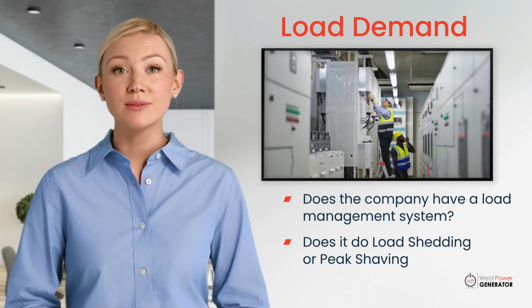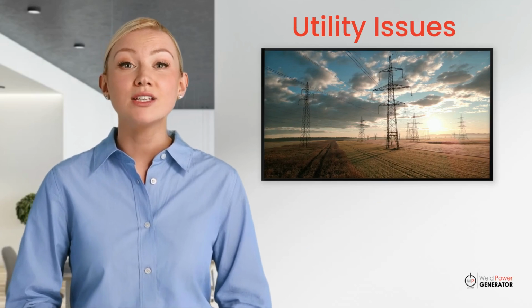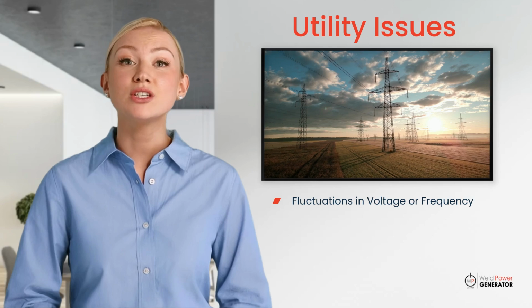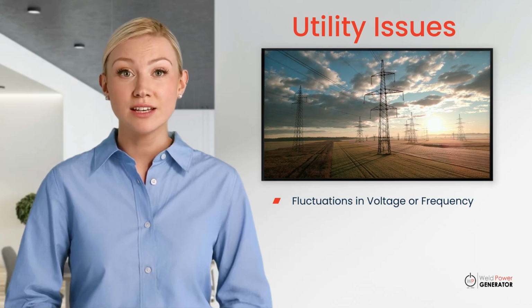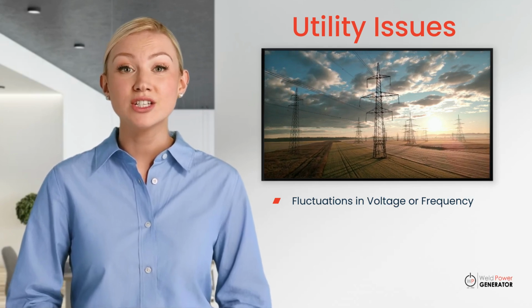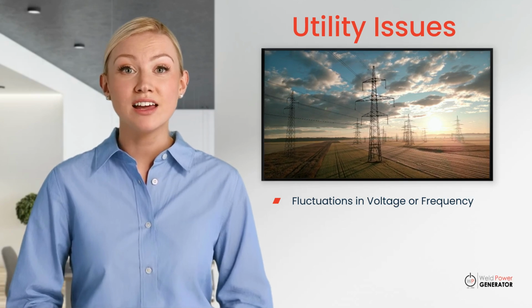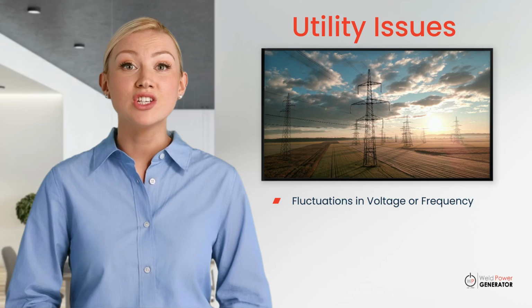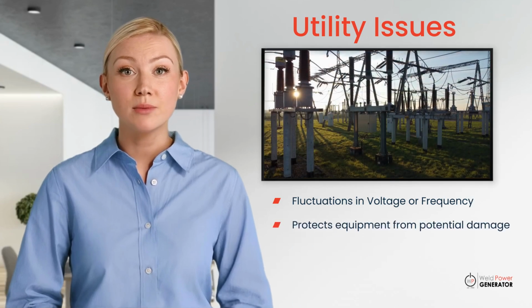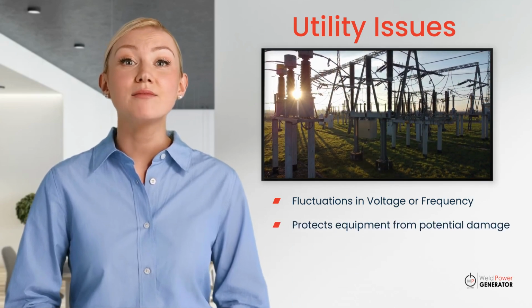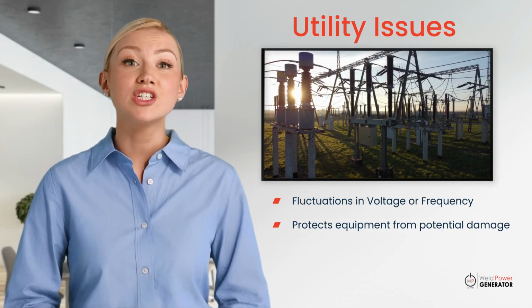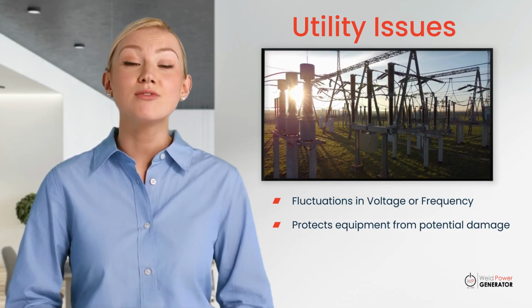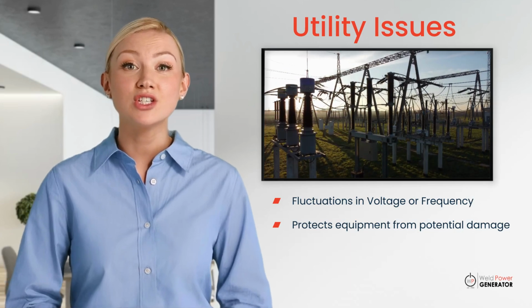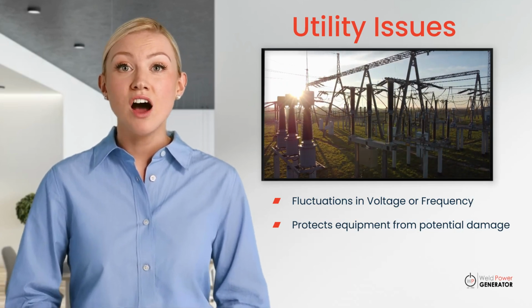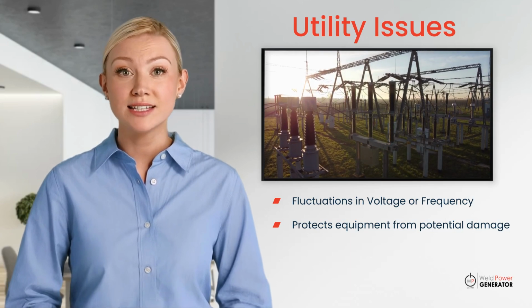Even when utility power is present, fluctuations in voltage or frequency can trigger a generator's start. Sensitive ATS units may detect these irregularities and preemptively switch to generator power to protect equipment from potential damage. Investigating power quality issues with an electrical engineer can help identify whether voltage sags, frequency variations, or harmonic distortions are causing the generator to start unnecessarily.